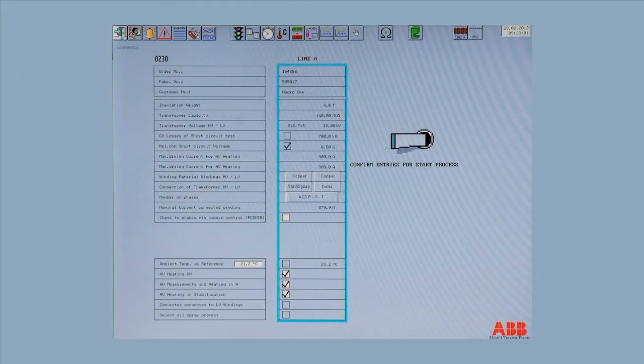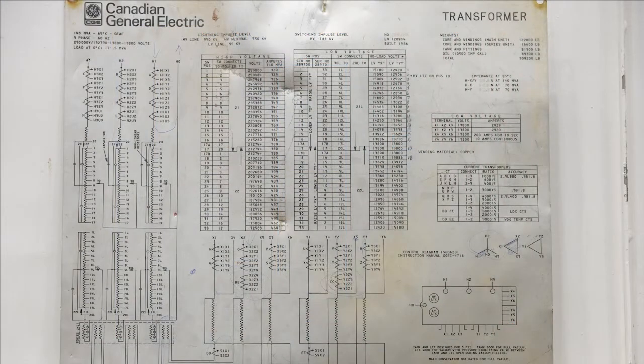Overview. Data input and process start. The transformer's data should be entered in the transformer data screen. It is recommended that these parameters are cross-checked before starting the process to ensure that the correct values are entered. Wrong input of values can lead to current levels that can damage the transformer. The data should be checked against the data plate of the transformer and any available technical information.